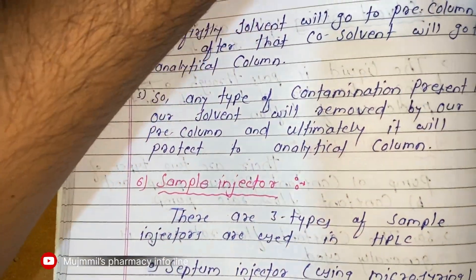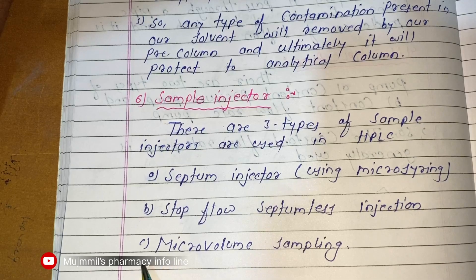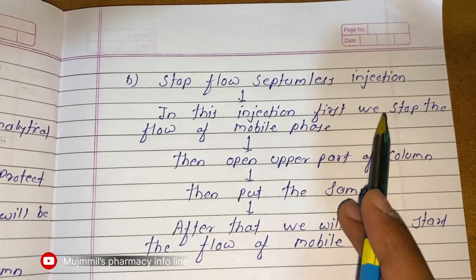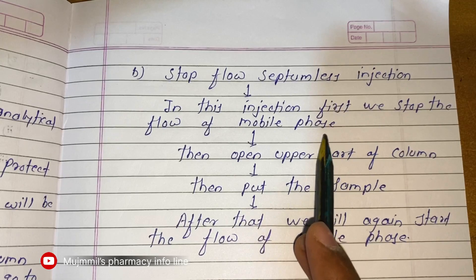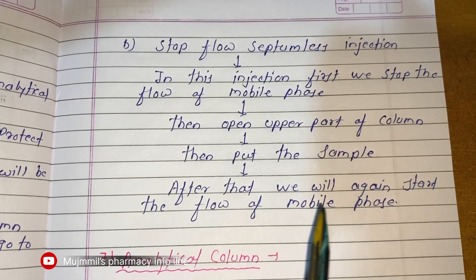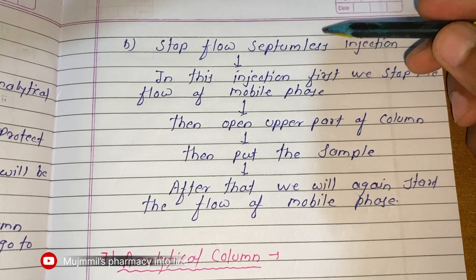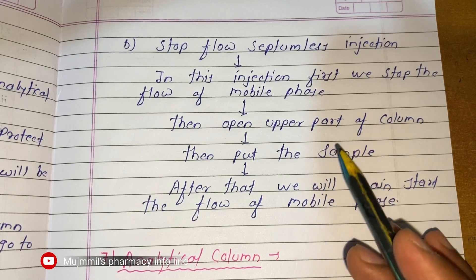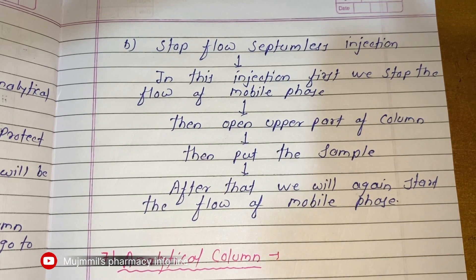There are three types of sample injectors used in HPLC: first, a septum injector using a microsyringe; second, a stop-flow septumless injection; and third, micro-volume sampling. In the stop-flow septumless injection, we stop the flow of mobile phase, open the upper part of the column, put the sample in, and then restart the flow of mobile phase. This is the concept of the sample injector.